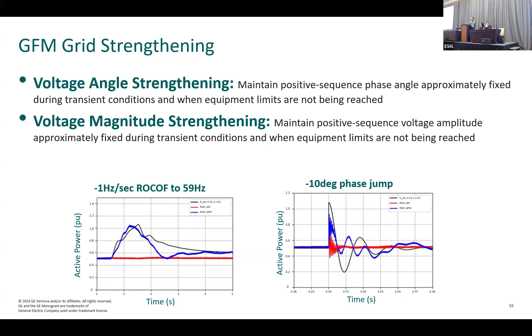In this case the grid-forming turbine behaves roughly as a synchronous machine with an inertia of three seconds and a reactance of about 30% in per unit. For the phase jump test — a negative phase jump — the desired result is a positive boost in active power. The grid-following device still has a little bit of phase response because the PLL gets perturbed, giving a small instantaneous active power movement. However, it's not nearly as large or as long in duration as for the grid-forming case. If you integrate the area below the curve, the grid-following cases provide near zero energy, while the grid-forming resources — both synchronous machine and grid-forming wind turbine — provide significantly more extra energy.